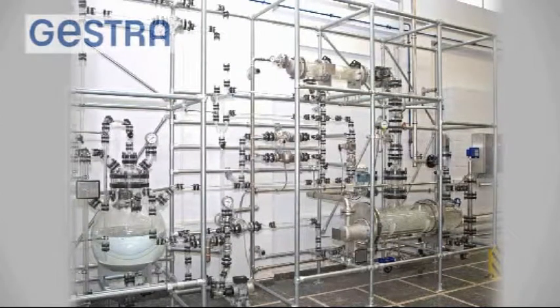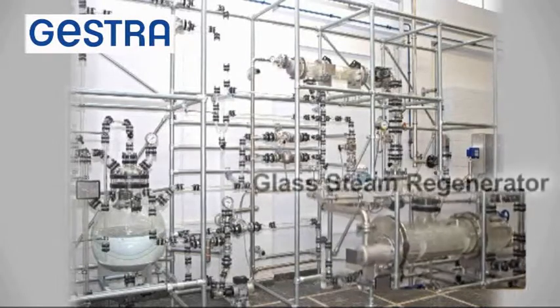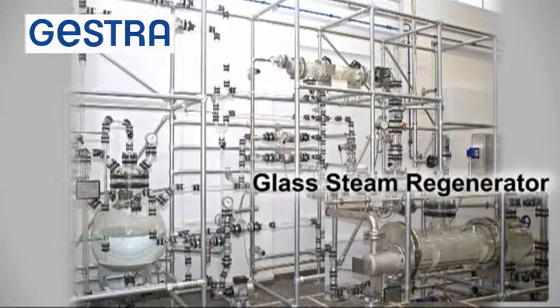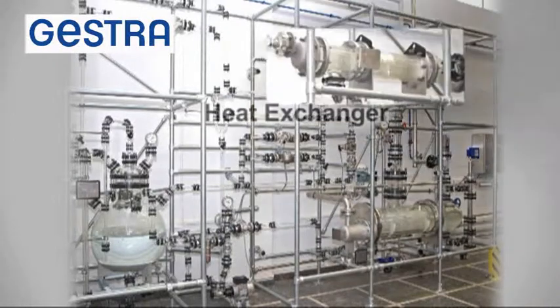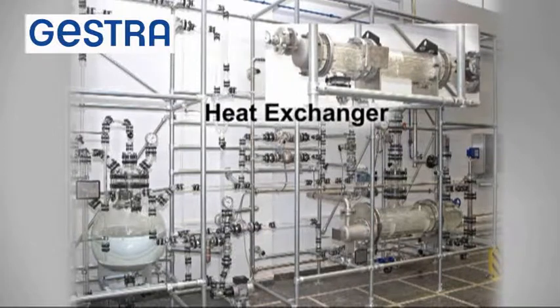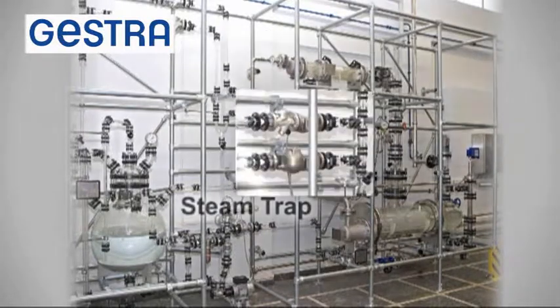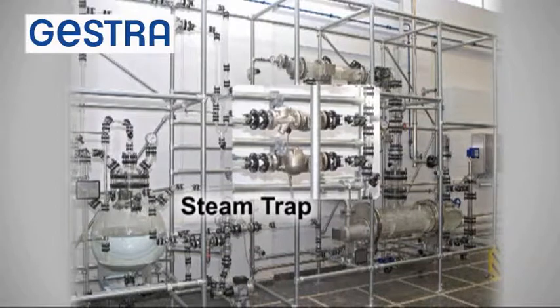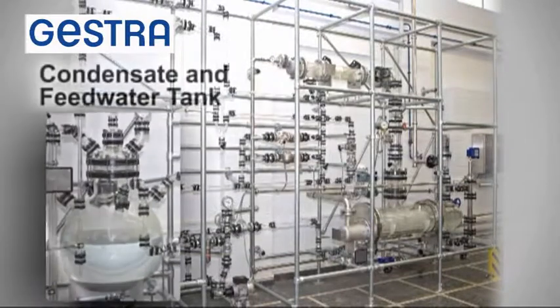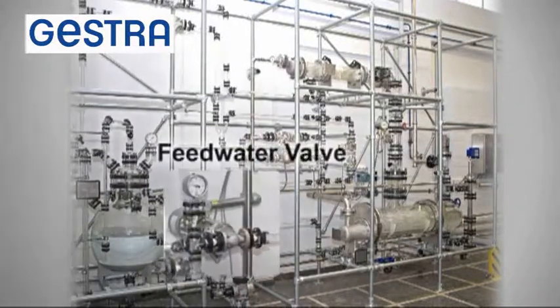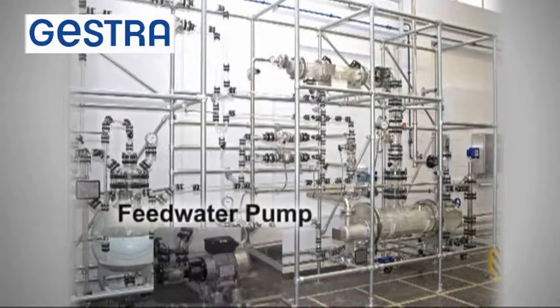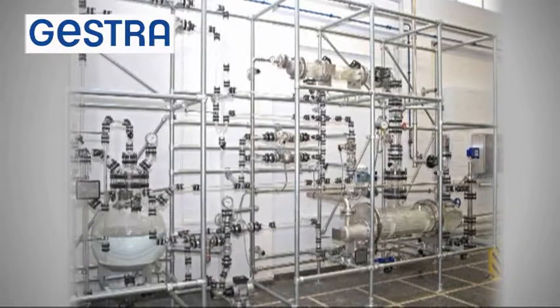GESTRA, an international manufacturer of valves and control technology, commissioned the world's first complete glass steam system in 2009. For the first time ever, it's now possible to look right into a steam generator and see how steam bubbles arise, how feed water is de-aerated, and how the various types of steam traps really work. A number of videos take a look at important facets of the steam condensate system and its operation. Thermodynamic processes taking place in the generation of steam, as well as during condensation, condensate discharge, and the origination of the water hammer effect are shown in a way that's easy to understand.